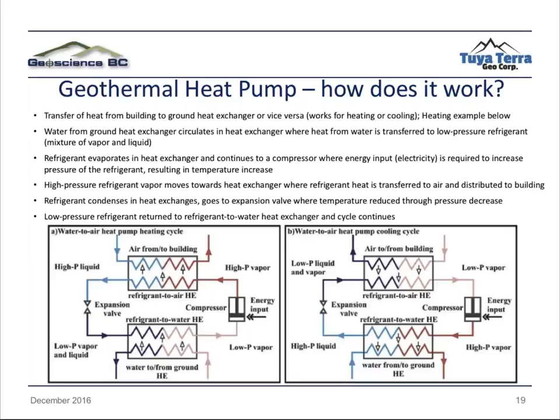The refrigerant condenses in a heat exchanger, goes through an expansion valve where the temperature is reduced and the pressure is also reduced. And then this low pressure refrigerant is returned to the refrigerant to water heat exchanger, and the cycle continues. So all that really means is that the heat is then exchanged from the refrigerant through that heat exchanger to the water that goes into the ground, and then the cycle just keeps continuing. And so this cycle is reversed when dealing in a cooling cycle.